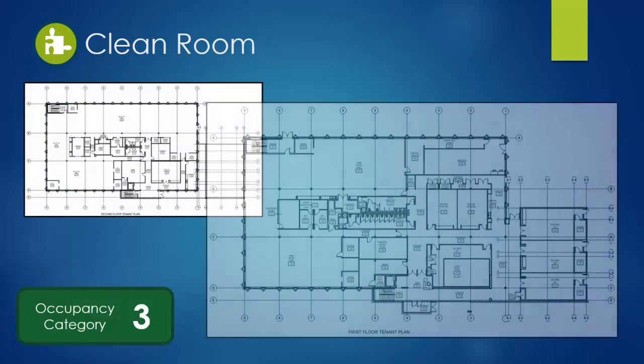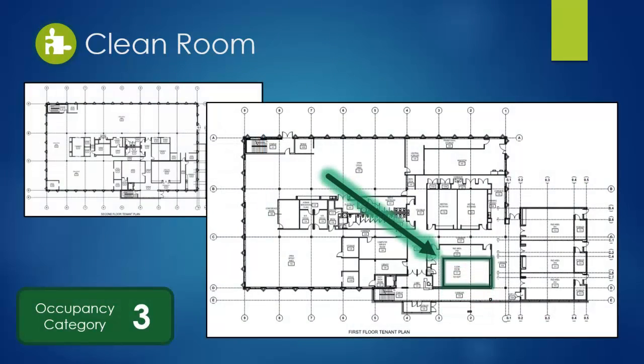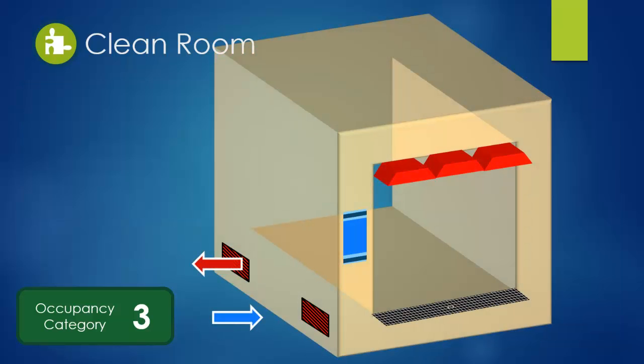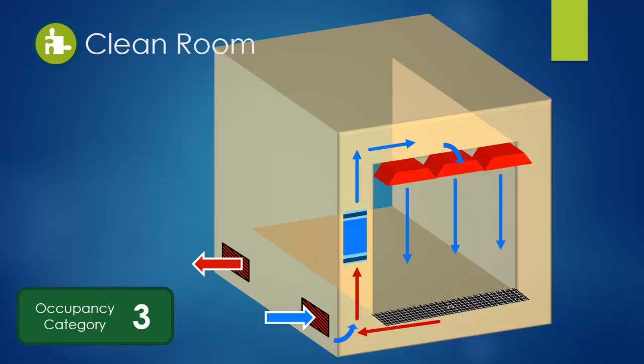Next, we will discuss the components within the clean room that makes up occupancy category 3. The required ventilation for the clean room will be taken from the adjacent research and development space through grills located near the floor at one end of the clean room. The incoming air will mix with the clean room return air and pass through a fan-filtered box which houses the required filters.